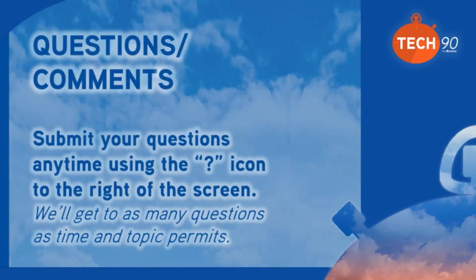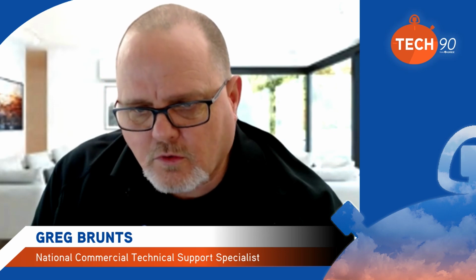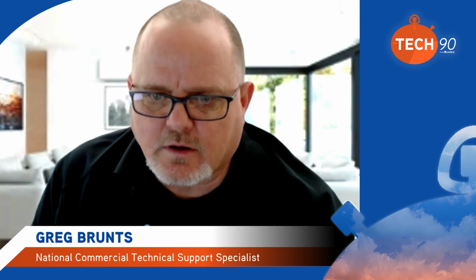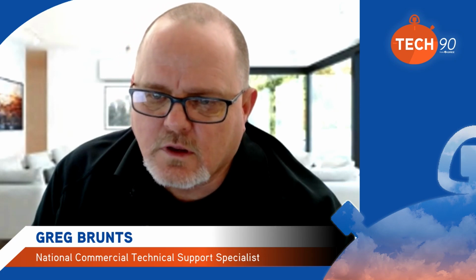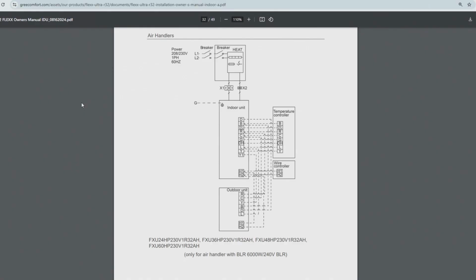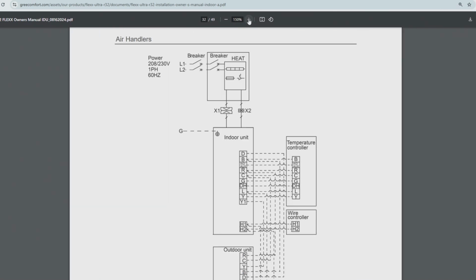Next question is from Matt. Said, what is the full operation mode if dehumidification terminal is energized during 24-volt control mode? And are we slowing the blower down? How is this different in the RS485 if used for control? That's a great question, Matt. Thanks for asking it. So as far as the dehumidification terminal, as you can see from the wiring diagram here, we do have a DH terminal on the indoor unit. If your thermostat has a DH terminal and it's an output and you get a 24-volt signal to the DH terminal on the indoor unit, that's exactly what it's going to do, is it's going to slow the blower down.